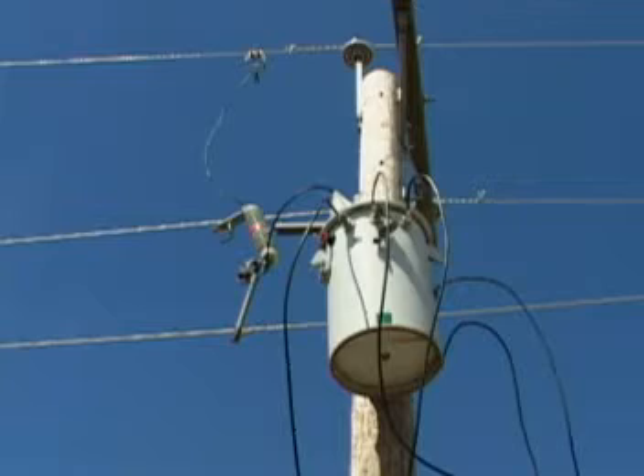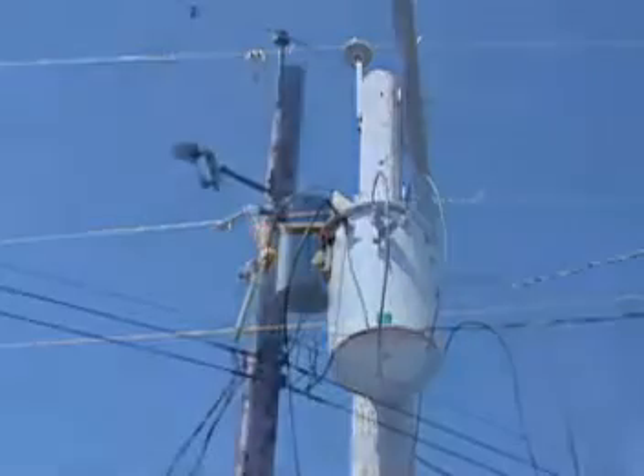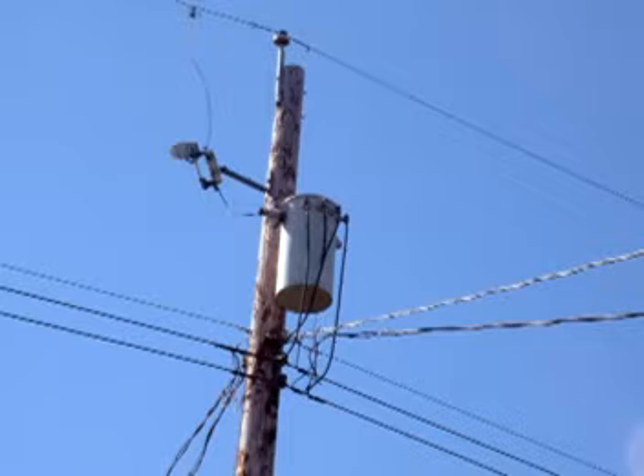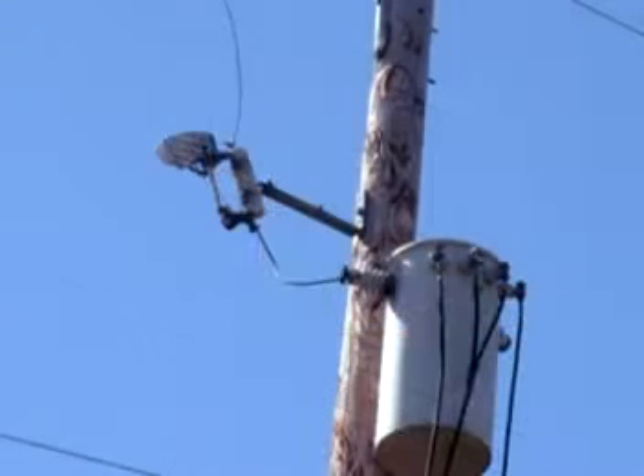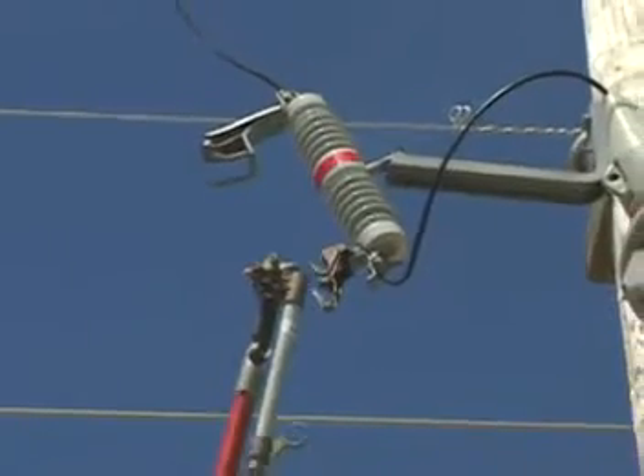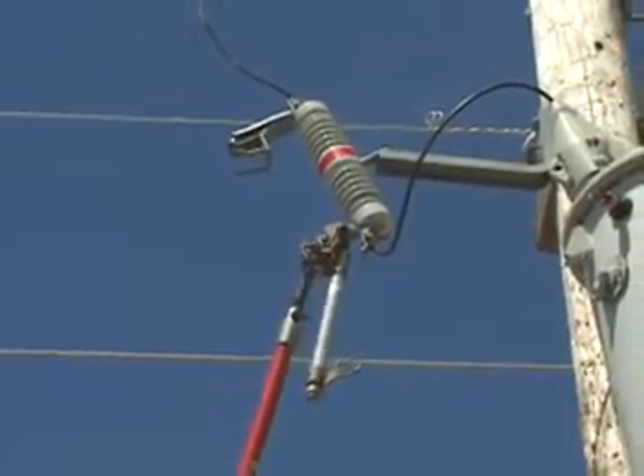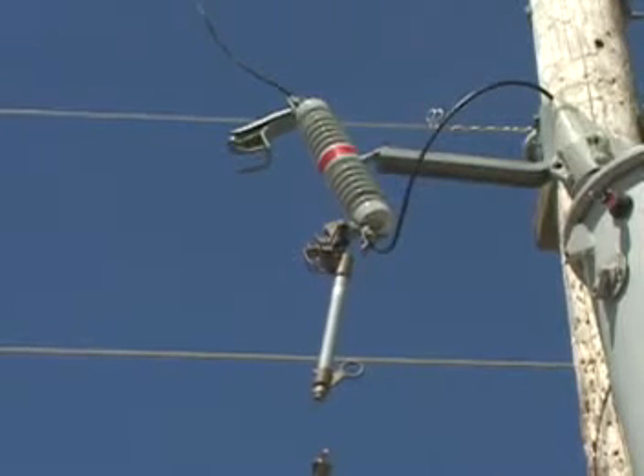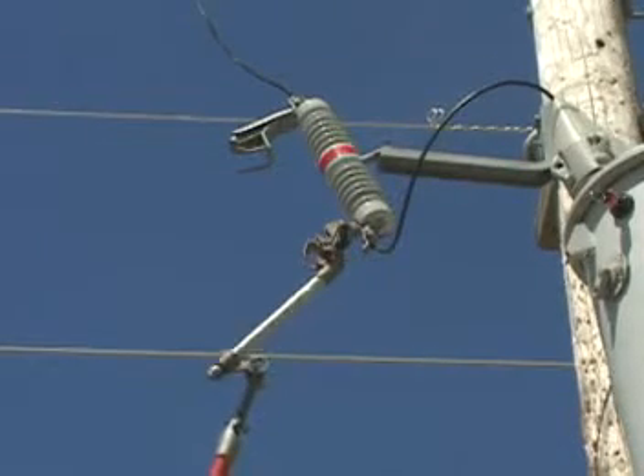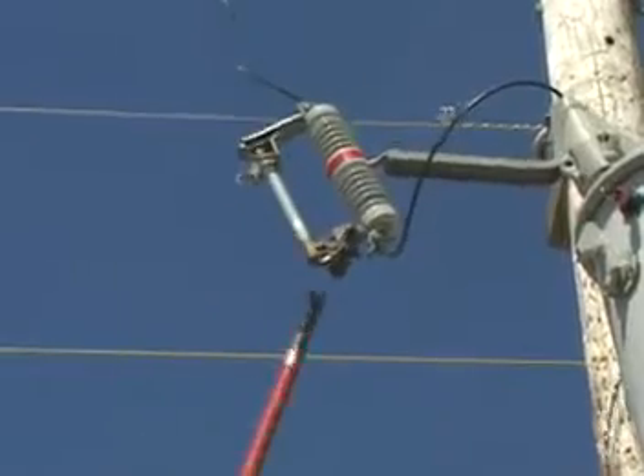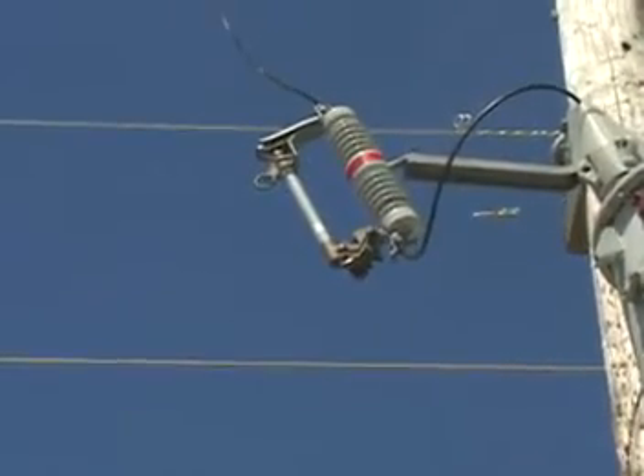Distribution transformers reduce the high voltage electricity from the supply network to voltages that are safe to use in homes and businesses. Pole-top transformers are usually connected to the primary supply network via a cutout fuse that protects customers and distribution equipment from overloads. Fault currents from the distribution network and evolving faults within the transformer will cause the fuse to operate. When an overload results in permanent damage to the transformer's internal components, an internal fault has occurred.